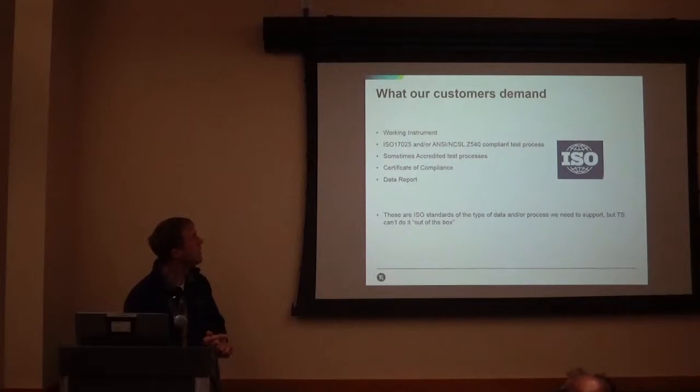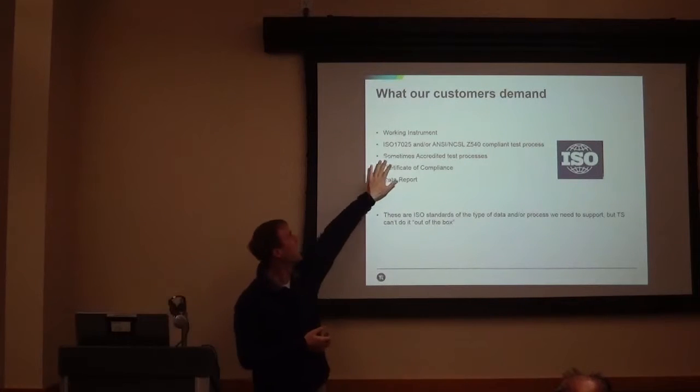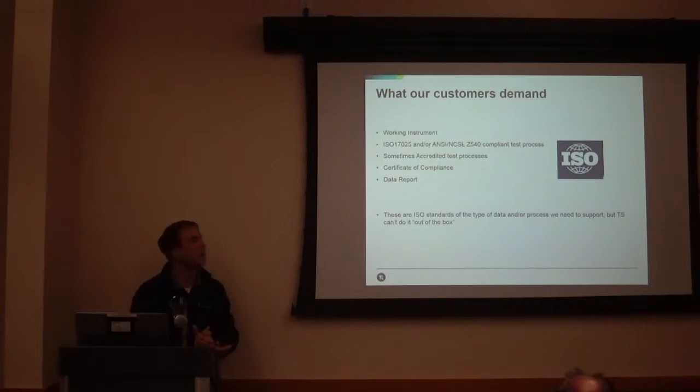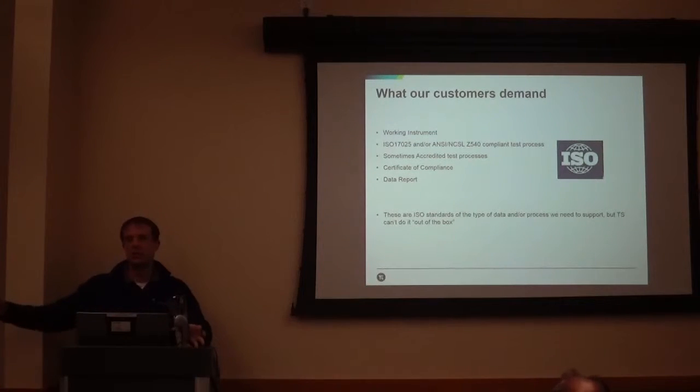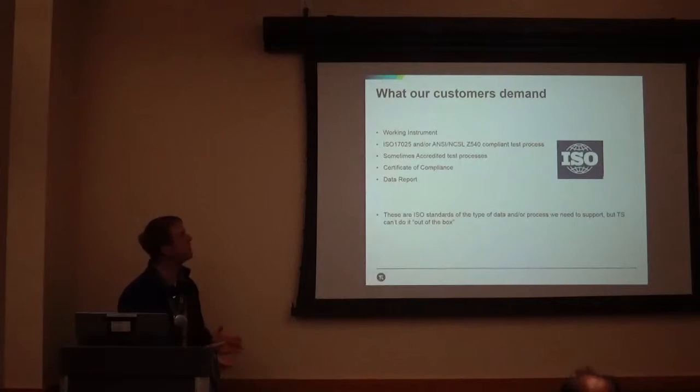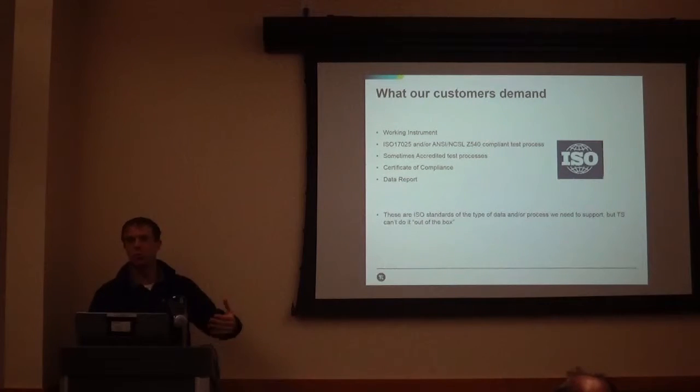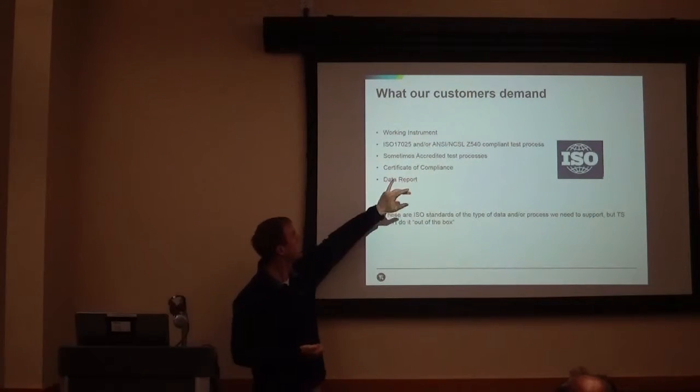Basically the idea behind either ISO 17025 or ANSI Z540 is putting together a metrology program that guarantees that when I say this is 1 volt, I have a traceable path of all those measurements and all that data back to whatever you want to define as the country or world standard of 1 volt or 1 second. And whether you believe us or we go off and get it accredited by another laboratory that says, yes, we're doing it right, is where we get accredited.